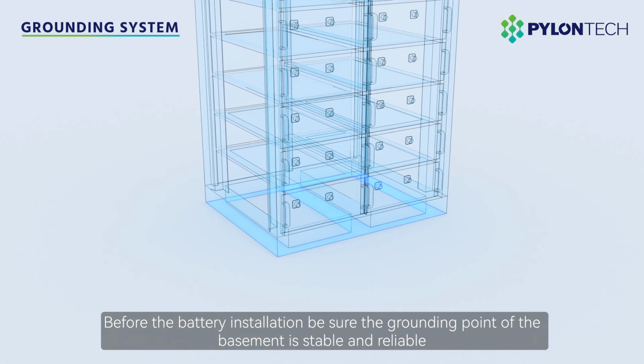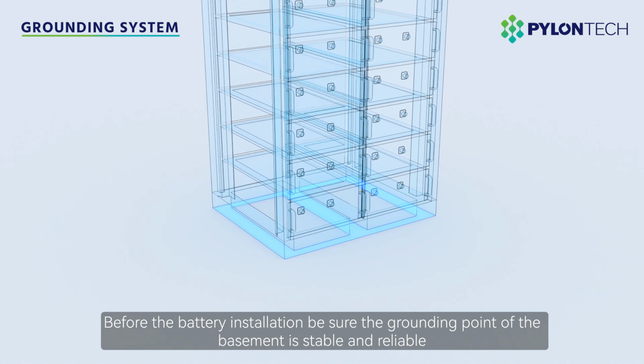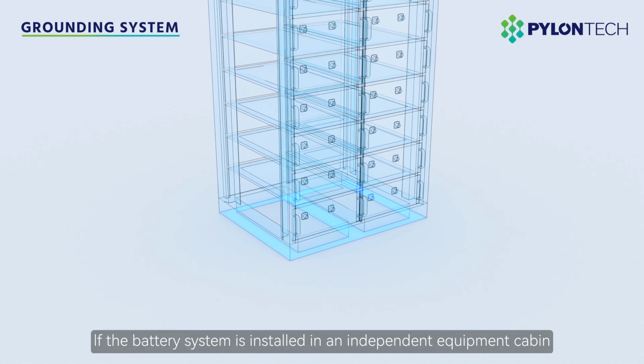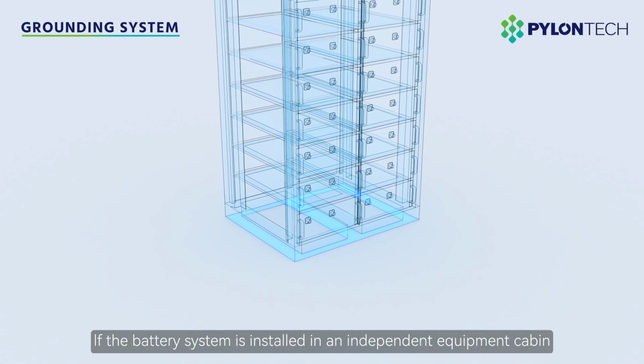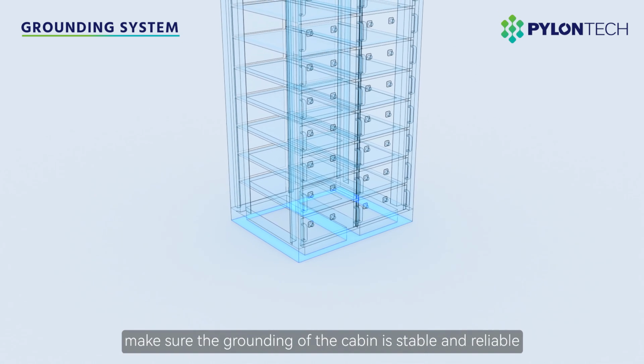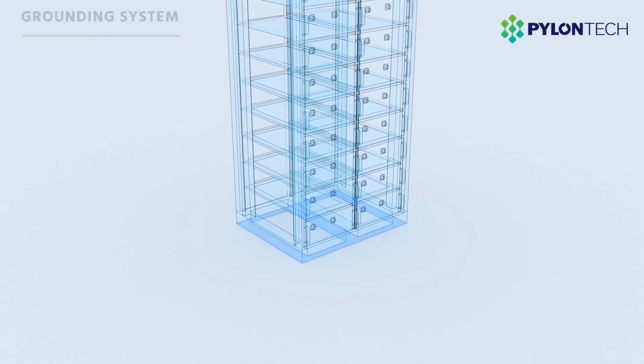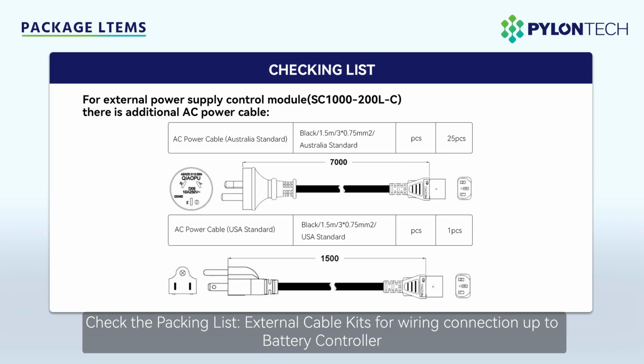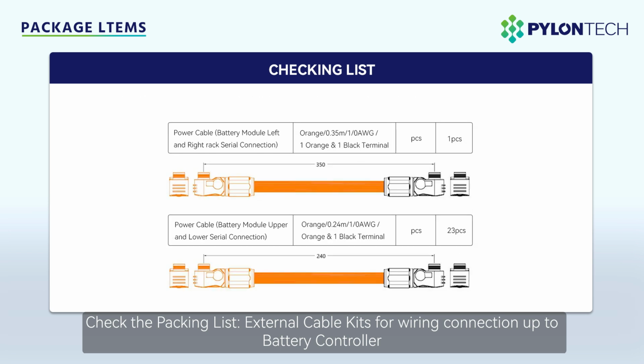Before the battery installation, be sure the grounding point of the basement is stable and reliable. If the battery system is installed in an independent equipment cabin, make sure the grounding of the cabin is stable and reliable. Check the packing list. External cable kits for wiring connection up to the battery controller.